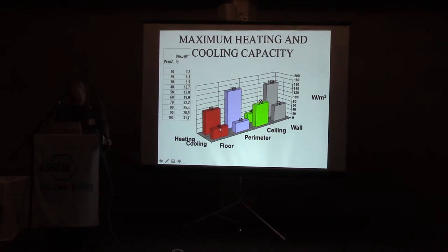And floor temperature we could go down to 20, so that's a delta T of 6 times the heat exchange coefficient of 7, that gives you 42 watts per square meter. And the same you can do for the others. So for the ceiling you could go up to 100 watts per square meter for cooling, and down to about 40 for heating. So that's how you come to the boundary conditions for your system.